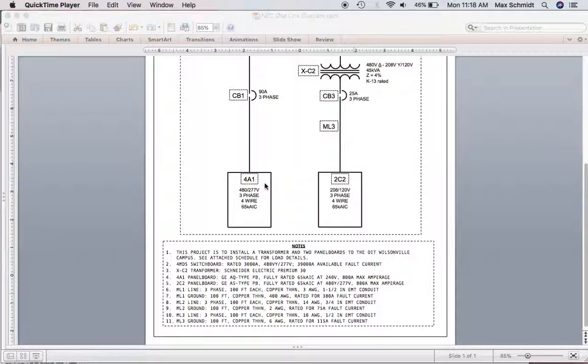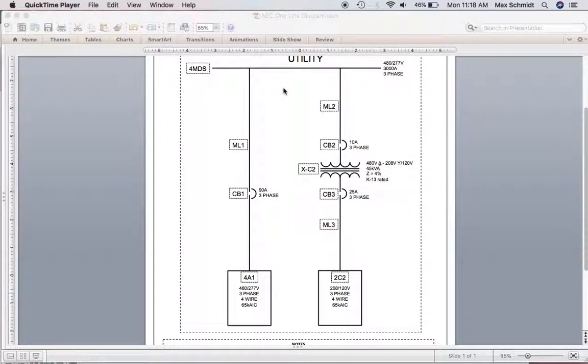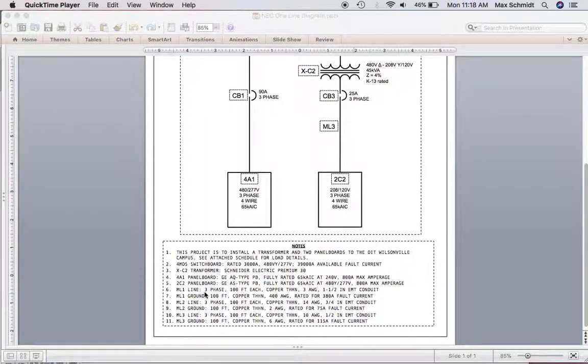So for sizing the main lines, I went and looked at how much power each of these two panel boards were providing to their loads to see how much current they'd be drawing from the utility. So I went and sized it from there. So for my main line 1, it's going to be 3-phase, 100 feet each, as said in the project description, copper THHN line. All of these lines are copper THHN, and then they are all different gauges. So my main line 1 is 3 gauge, and then the grounding wire to handle all 3, say there's a line to ground fault, is going to be 400 gauge. There's the most current going through this line.